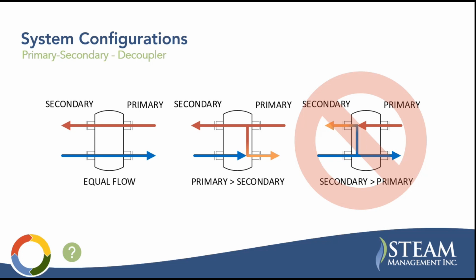The last scenario is if your secondary pump is out-pumping your primary loop, and that's a situation you want to avoid, because you are mixing cold water in with your intended hot water that's supposed to be going out to the system. You're not hitting your supply temperature, and that can cause control problems, nuisance trips, and obviously reduce comfort levels in your system because it's not operating as intended.